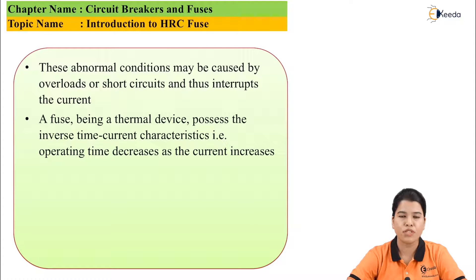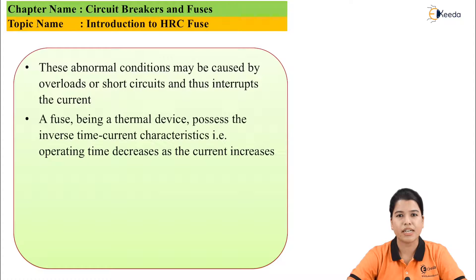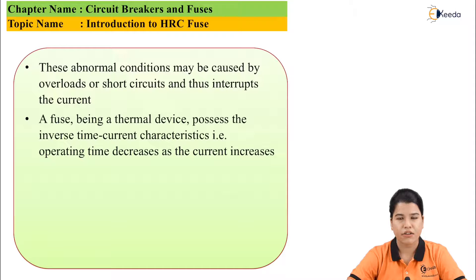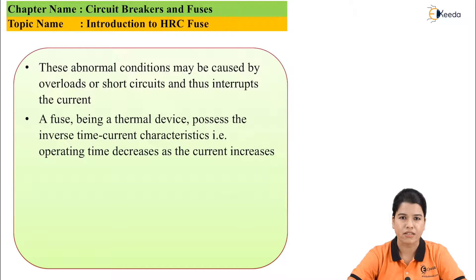As the fuse is a thermal device, it consists of an inverse time-current characteristic. The meaning of inverse time-current characteristic is that as the current goes on increasing, the time of operation goes on decreasing. Which means, if the fault current rises to a high value, the time required for the melting of the fuse element will be very less.